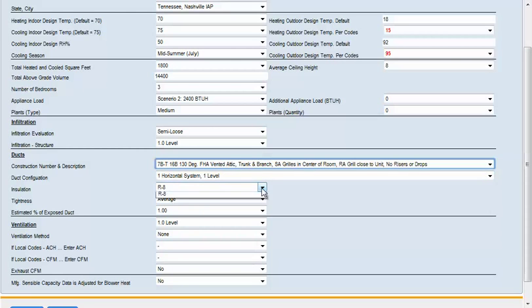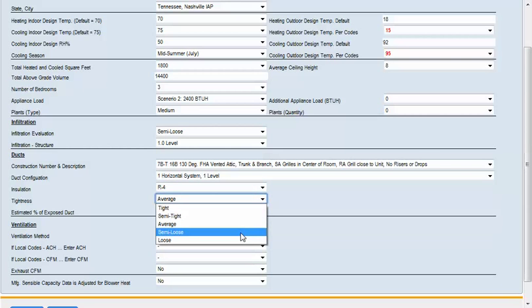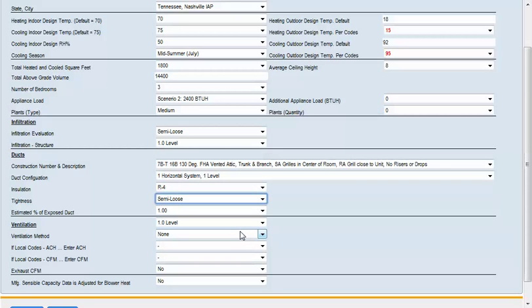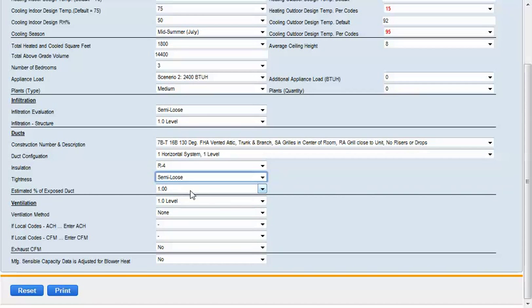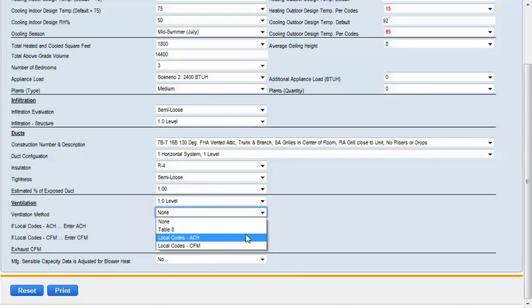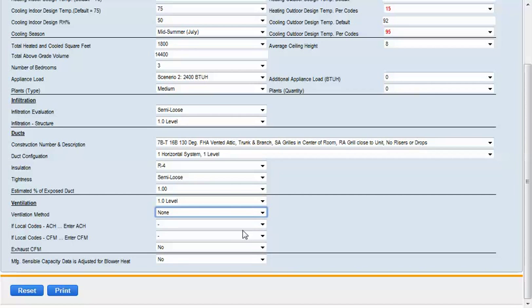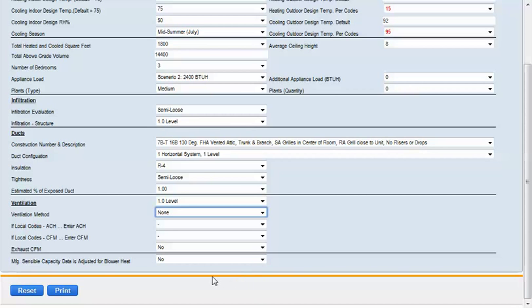Our insulation we're going to change to R4 and our duct tightness we're going to change to semi-loose here. 100% of the ductwork is exposed. For ventilation we're not going to select anything, but if you did you could select the table from the book or if your local codes require air changes per hour or CFM you could enter that. Since our manufacturer's sensible capacity data is not adjusted for blower heat, we would leave that answered no.